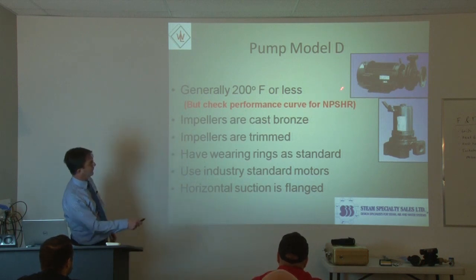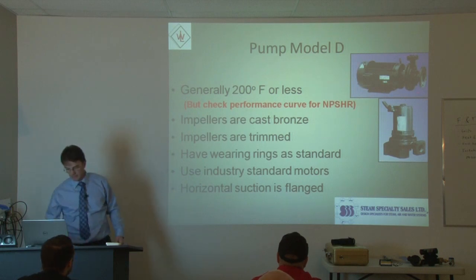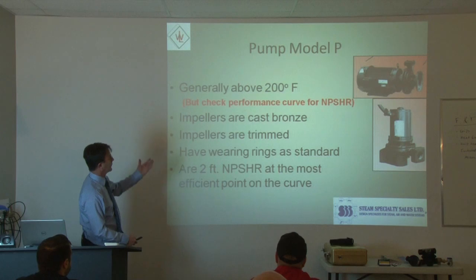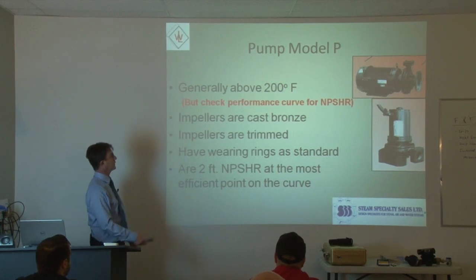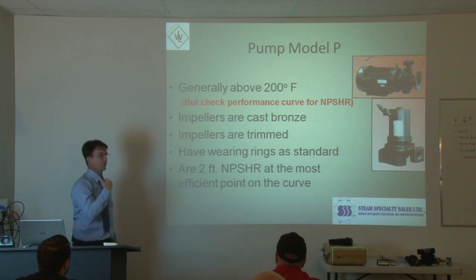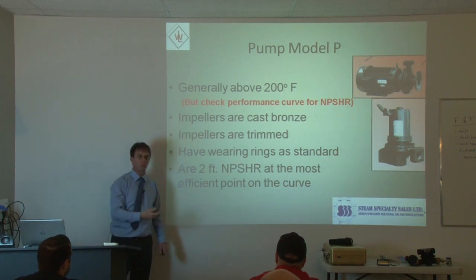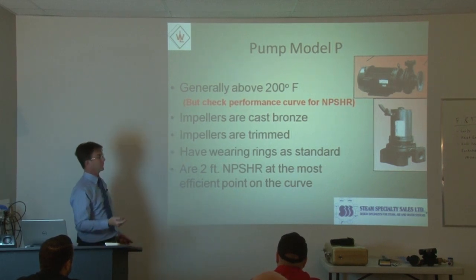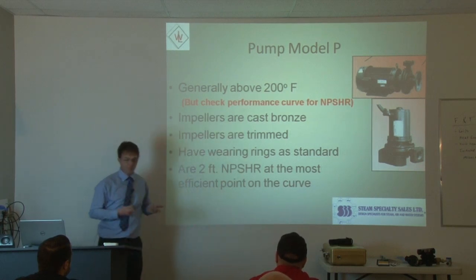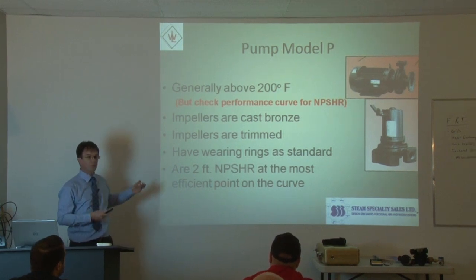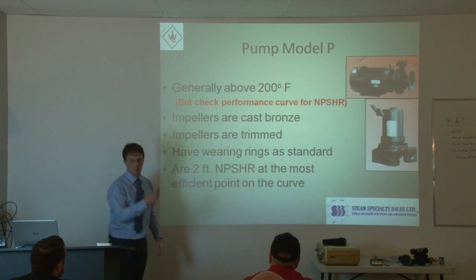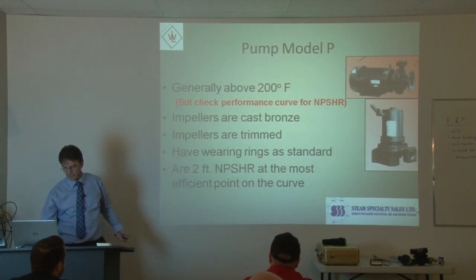Horizontal suction is flanged - they have either horizontal or vertical, depending on space required or customer preference. Model P is for higher temperatures or higher pressures. They also use them in Denver because it's 5,000 feet above ground. The lower pressure means a lower boiling point, so condensate reaches boiling point much quicker than at sea level. That's why they use Model P pumps in higher elevations.